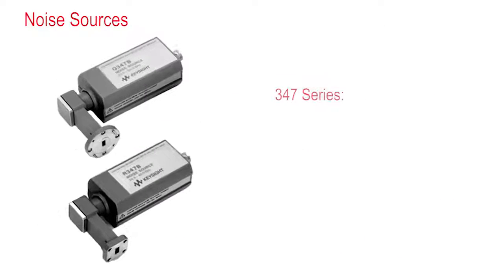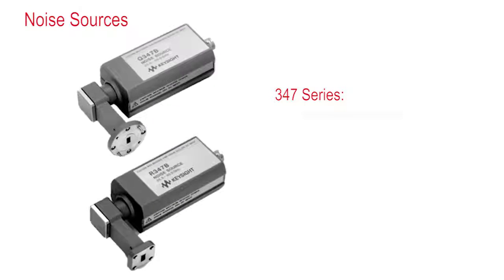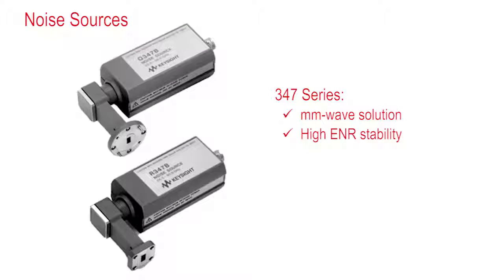The 347 series is Keysight's millimeter wave solution with high ENR stability in the long term. This stability means longer calibration cycles and more reliable measurements. The sources are banded and interfaced with waveguides rather than cables or coax.